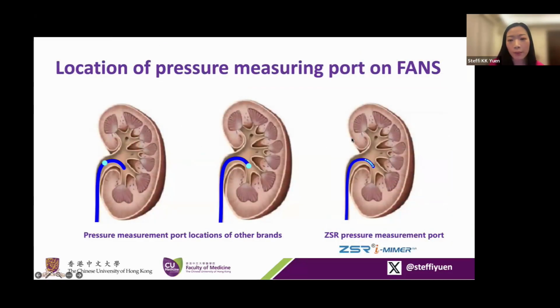The location that I've previously mentioned of these pressure measuring ports on the IRP monitoring FANS varies from brand to brand. For the rightmost, it is a ZSR i-MIMER FANS. There are multiple small, tiny channels that are transducing the pressure to the sensor. There are other brands on the market where the pressure measuring ports are located at the very tip with a single channel, or at the juncture between the relatively straight and flexible part. So the point is, if you are using these FANS in the tight ureter, if it's not put across the UPJ, then you might not actually be measuring the accurate pressure.